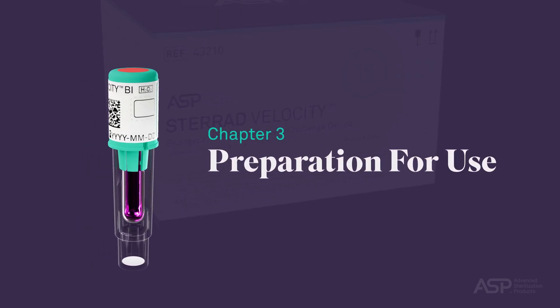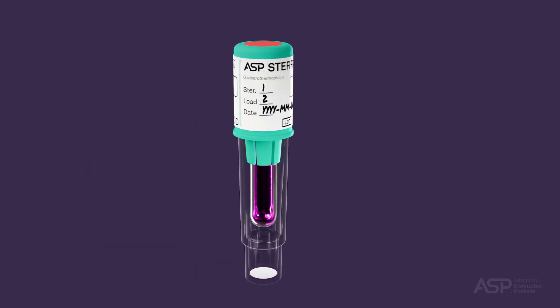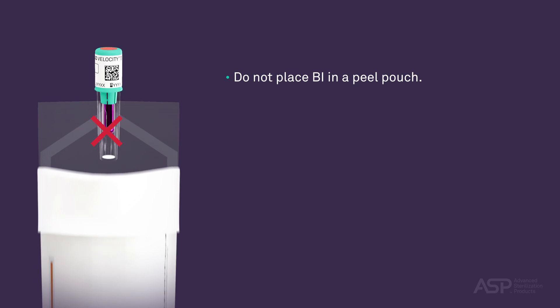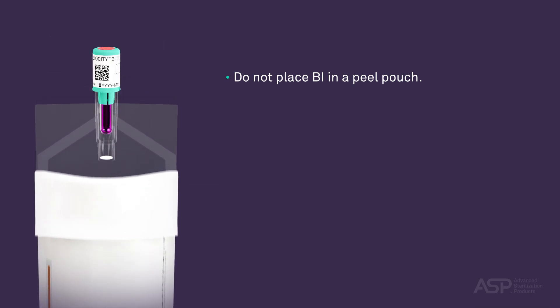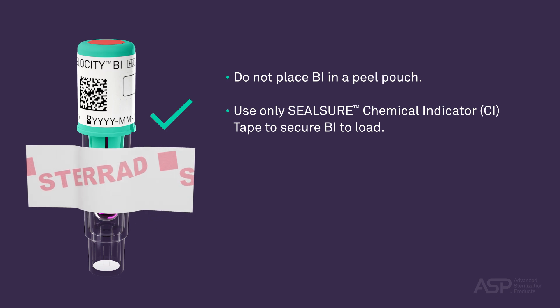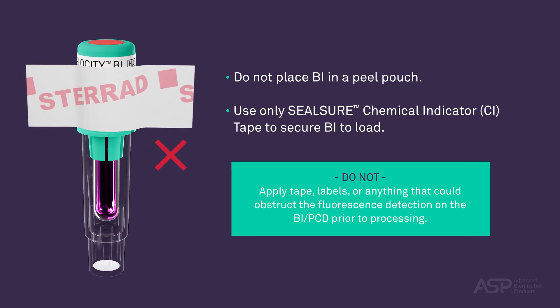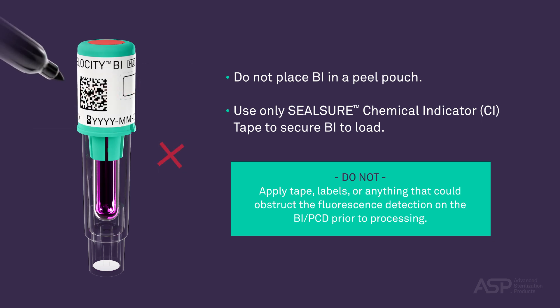Preparation for Use. When preparing a STERRAD Velocity BI PCD to monitor a sterilization cycle, do not place it in a peel pouch. If you are applying tape to secure the BI PCD to the shelf, you must use Seal Sure Chemical Indicator (CI) Tape. Do not apply tape, labels, or anything that could obstruct the fluorescence detection on the BI PCD prior to processing. The tape or labels will block the sterilant ingress windows, causing misleading results. Additionally, do not place marks on the barcode, as this may interfere with the barcode reader's ability to retrieve barcode data.